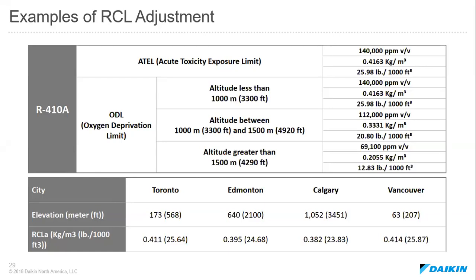For example, at sea level, we're right at that 25.98 pounds, or 26 pounds, per 1,000 cubic feet. If our altitude increases to 1,000 meters or 3,300 feet, then our refrigerant concentration level will start to slightly decrease at that altitude and higher. So it'll actually go to 20.8 pounds. And then if we're at an altitude that is greater than 4,290 feet, then we're going to be at 12.83 pounds. So actually, we have lower refrigerant concentration limits when we're located in a locality that is at a high elevation, as I show below here, such as Calgary, Canada.